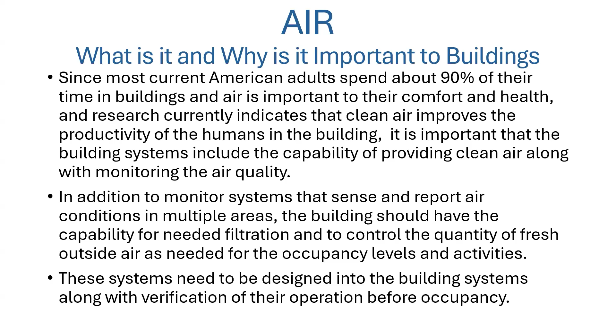ASHRAE, just recently on February 12th of this year, 2025, reviewed multiple studies about CO2 levels. For many years it was said that 1,000 parts per million could be a limit, but based on research they've decided 1,000 is not an absolute limit for all spaces. That throws a wrench in setting a standard, but these levels can still be used for monitoring and building ventilation control systems, and most systems do.